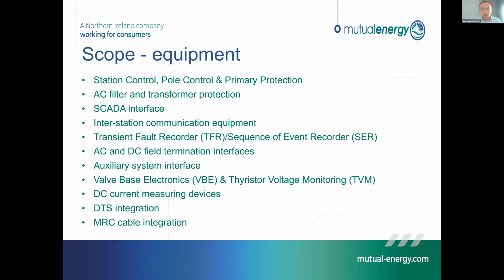So I won't, for the sake of time, go through this in detail, but just to say that in terms of the equipment, we're replacing a lot of the control and protection equipment, and there is some work on the auxiliaries, the valve-based electronics, and thyristor voltage monitoring, and some of the measurement devices. We're looking to integrate the DTS system, for the measurements of cable temperature along the route. And also the current system is blind to the cable changes that occurred back in 2016. So we're giving the control system visibility of what that cable setup is now.